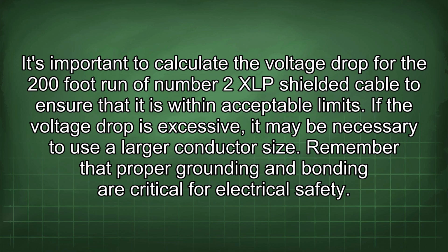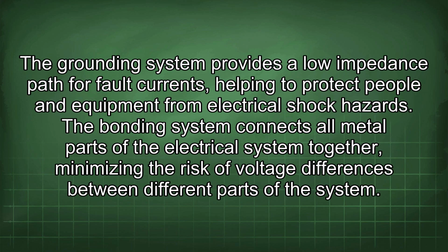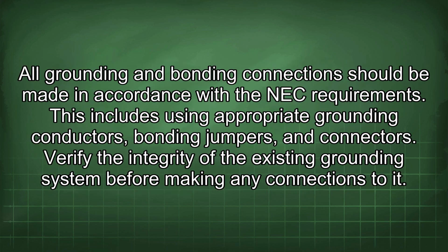Remember that proper grounding and bonding are critical for electrical safety. The grounding system provides a low impedance path for fault currents, helping to protect people and equipment from electrical shock hazards. The bonding system connects all metal parts of the electrical system together, minimizing the risk of voltage differences between different parts of the system. All grounding and bonding connections should be made in accordance with the NEC requirements. This includes using appropriate grounding conductors, bonding jumpers, and connectors. Verify the integrity of the existing grounding system before making any connections to it.